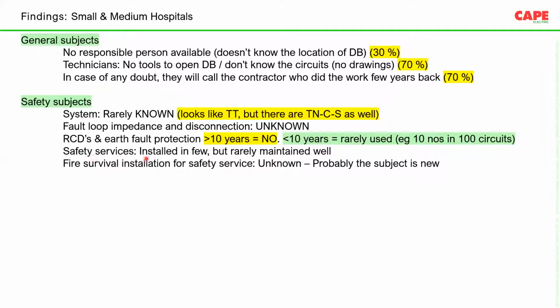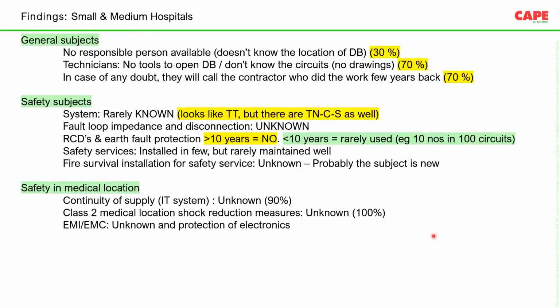Then the safety services, which are firefighting and other systems. In most of the larger places, 100 kilowatt, 200 kilowatt, 300 kilowatt, the larger multi-storied buildings, firefighting systems are installed, but only for namesake. Fire survival installation for fire safety, if we ask, is generally unknown. Probably the subject is quite new for those engineers.